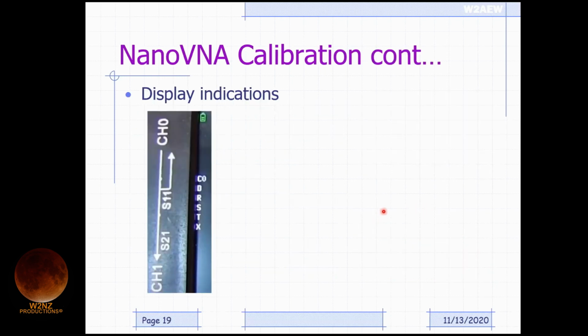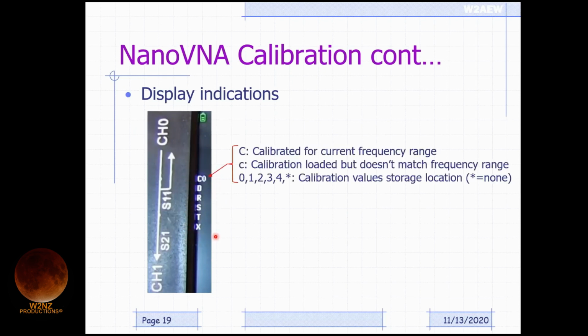On the unit itself, the calibration indications are way over on the left-hand border of the display. The capital C indicates that over the frequency range you're looking at, we are currently calibrated. If that letter is a small c instead of a capital C, it means you've got a calibration loaded, but it doesn't match the measurement frequency range you have set up, so you're doing interpolation. And the number that follows indicates which memory location the current calibration is being used from. So if I've stored a calibration in slot number 2 and recalled it, this would say a 2 here, okay?